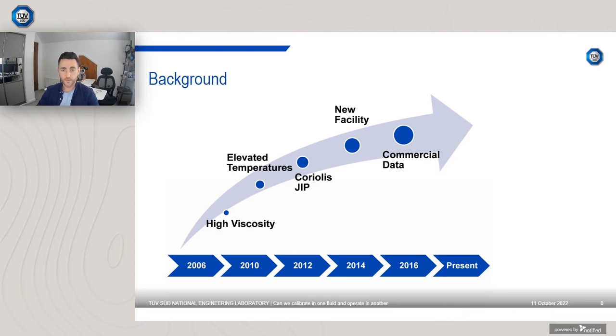And there were various different outcomes, but the main outcome was that there was a requirement for a new flow facility that could calibrate flow meters at process conditions, so as close to service conditions as possible with respect to temperature and pressure, due to those temperature and pressure effects that I've already mentioned. So we, again, applied for UK government funding in 2014 and designed and built that facility within around about 18 months' time, had that facility ready. It was extremely successful and it's been operating since then.